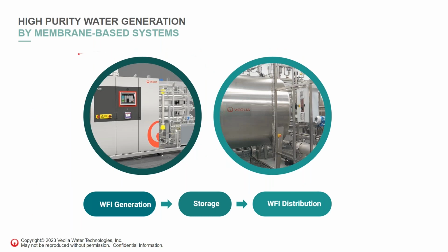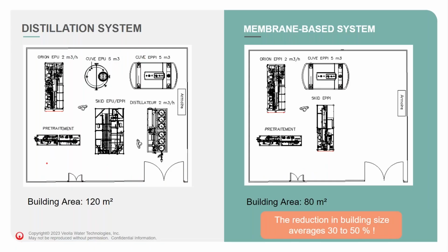So from the picture we had before, where we had 5 stages of trying to get to WFI water using distillation method, if we go the cold WFI route using just the RO EDI storage and distribution, we come to this pictorial representation. So you have the generation system, you have the storage, and then the distribution side of the system. So we've removed some of the stages, which obviously saves us things on capital cost, etc., as well as, as we've just talked about, energy saving in some of the things we do with these sorts of products. So in terms of removing the other parts of the equipment, we can reduce the room size. Typically, reduction in building can be 30 to 50%, depending on the size of unit, because we no longer need a distillation unit as well as its pre-treatment and some storage and distribution items. So there is a clear saving in terms of the footprint for using cold WFI as opposed to a hot distillation system.